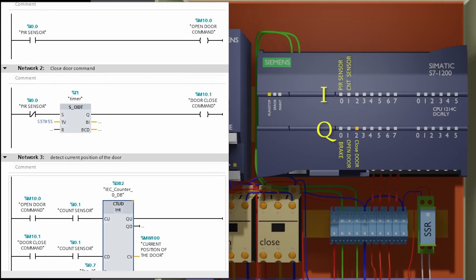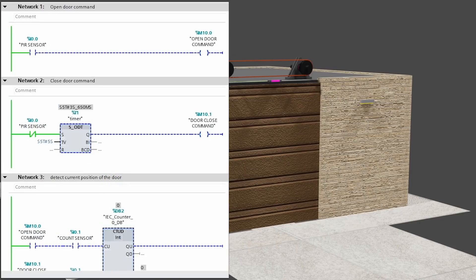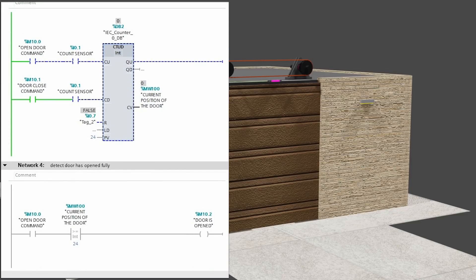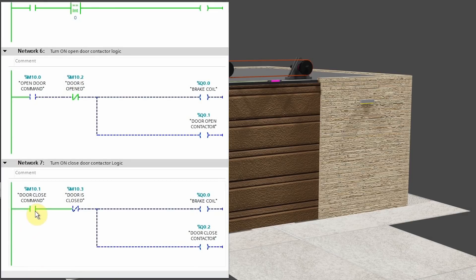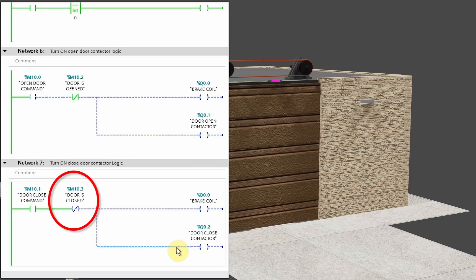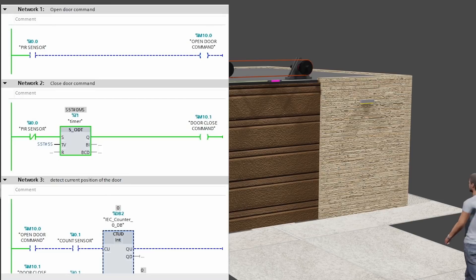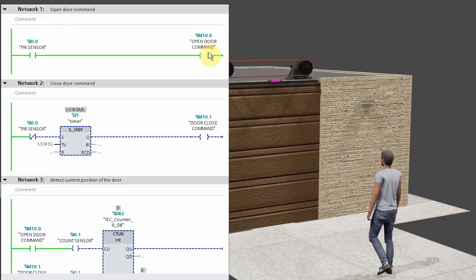Now let's test the programming. Right now there is nobody in front of the sensor, so the NC contact of the PIR sensor I0.0 stays closed, starting the five-second timer. Once the timer is over, it turns on the close door command bit M10.1. The counter value is zero, meaning the door is already in the closed position. In Network 7, the door close command M10.1 is on, but the brake coil and close contactor remain off because the NC contact of M10.3 is open — the comparison operation has turned on door closed bit M10.3. Now if somebody comes in front of the PIR sensor, it will turn on the open door command bit M10.0.